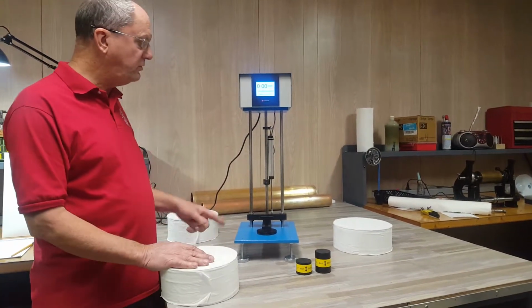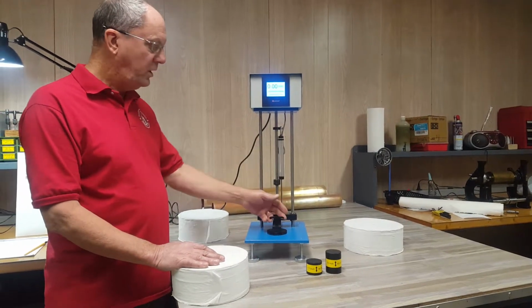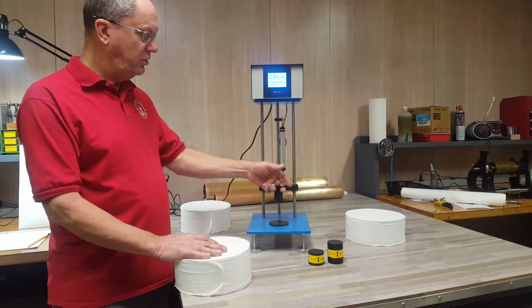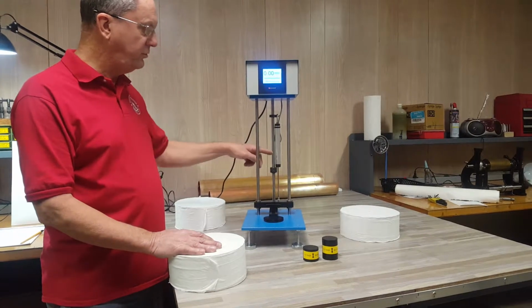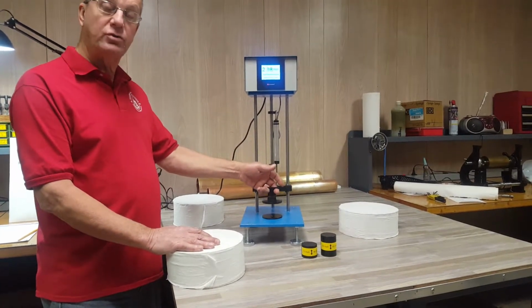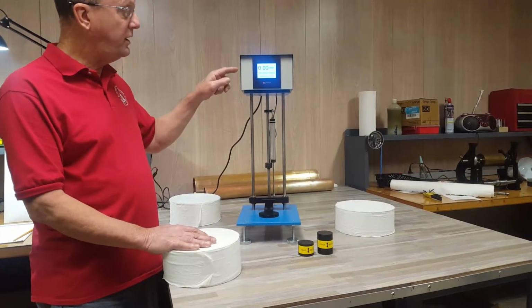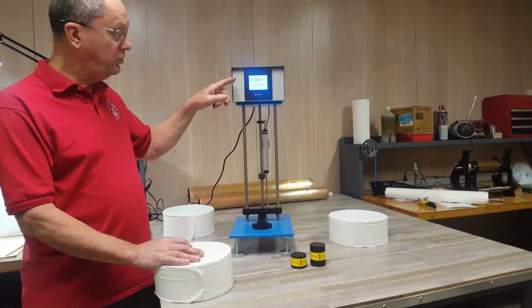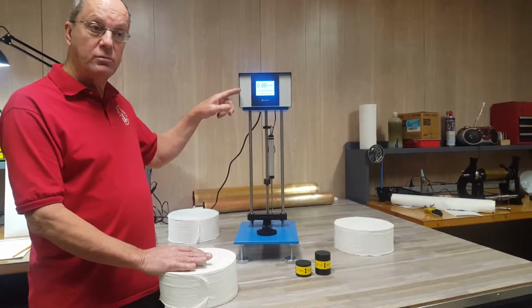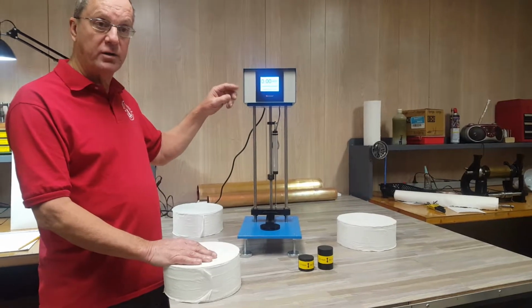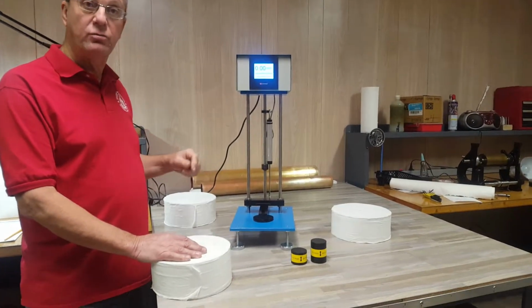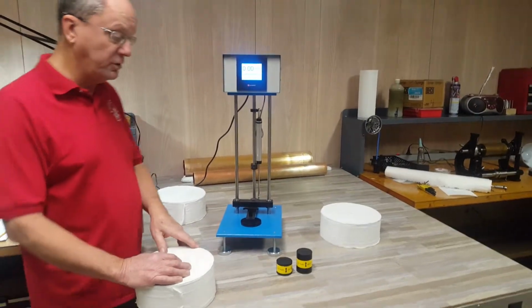The machine consists of 3 rails, and we have a caliper that moves on these 3 rails. We have a sensor in the back that measures the position of the caliper, and we have a touchscreen PLC that will display the width of the rolls and provide us with the calibration routine to calibrate this tester.